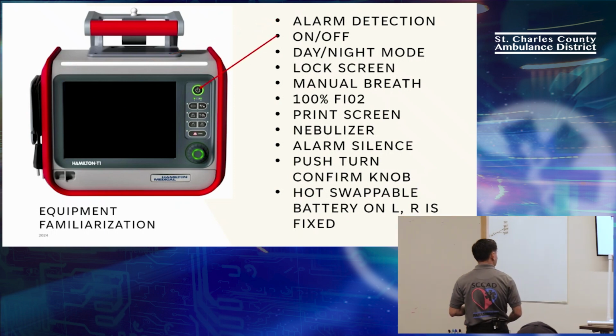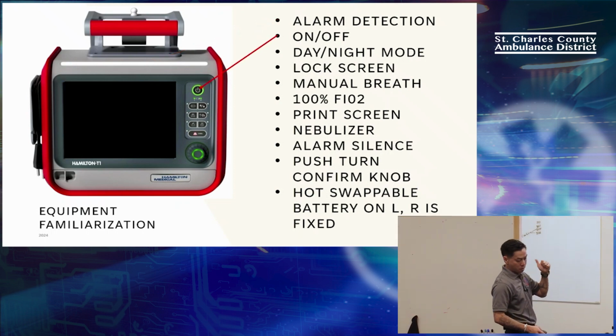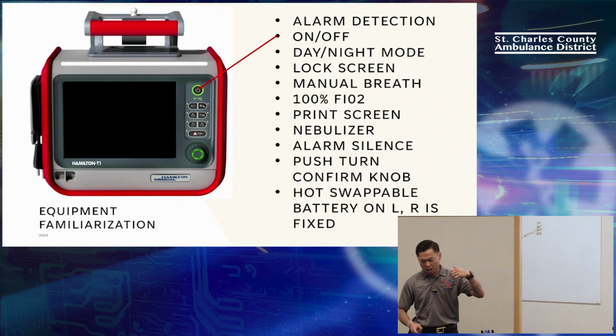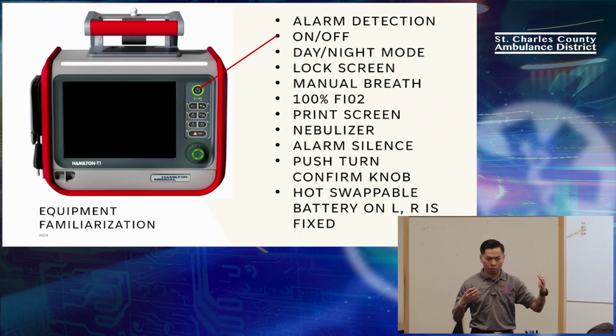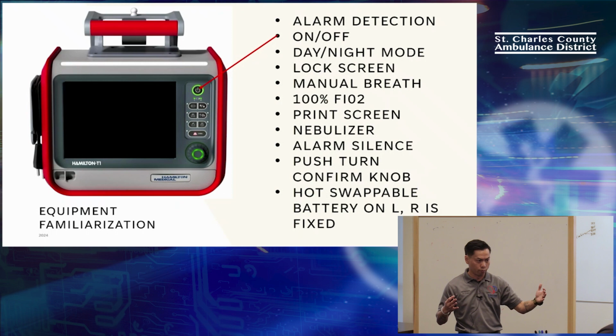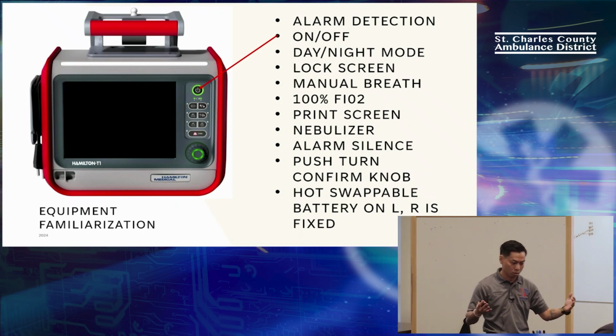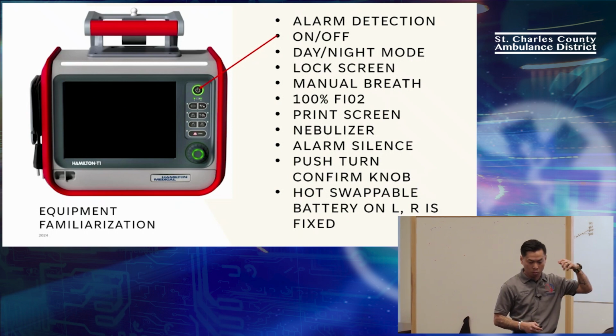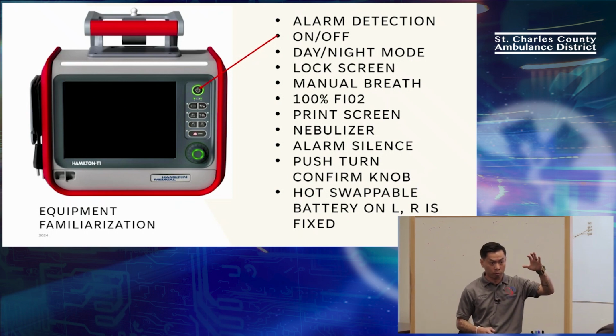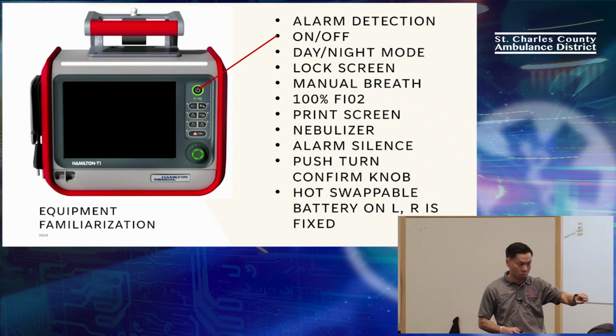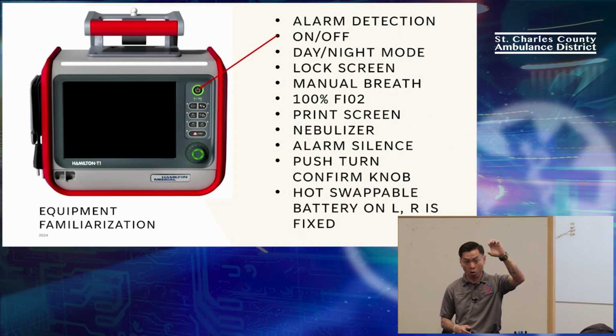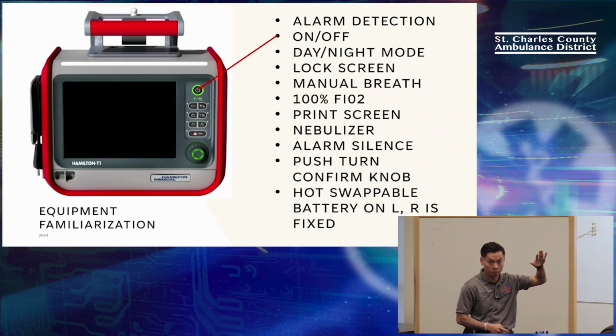The on-off button is a green illuminated button. You push it. It takes an annoyingly long amount of time for it to turn on, but it's not so long that the patient dies in front of you. You'll see it when we start doing it. The other cool thing about this is when you hit that button, it starts ventilation from the standby screen. So if you're on the standby screen, you could hit the start ventilation button on the touch screen, or you can actually just hit that on-off button and it starts the ventilations right away.